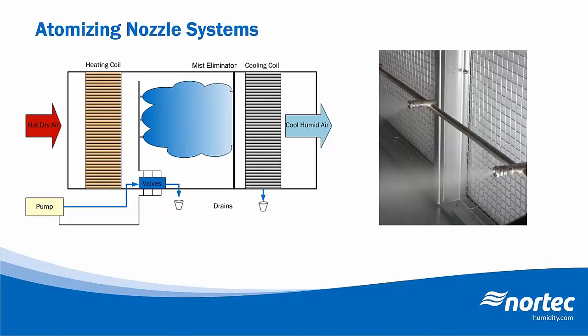I also mentioned that this type of system does require treated water, so either RO or DI water. So this is a requirement in order to ensure that there are no minerals that can precipitate out as the droplets evaporate, which could create a dust that can clog the mist eliminators or make its way down into the space as well. The treated water is also important to prevent scaling and clogging of the nozzles themselves.